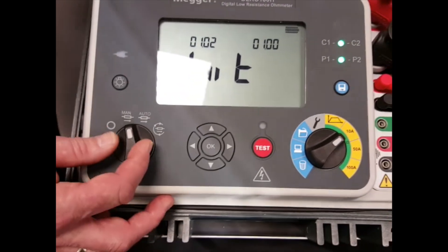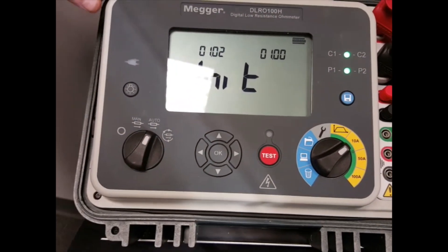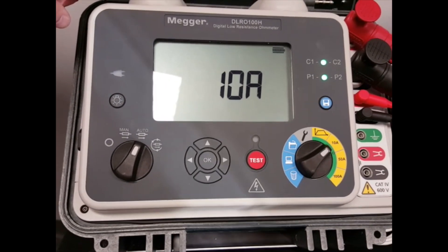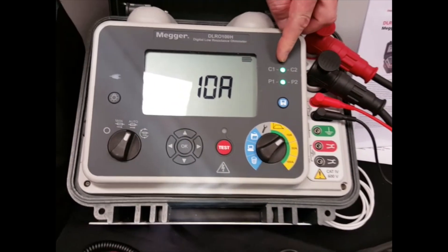In automatic over this side, this test is looking for continuity across the terminals. When you have continuity it will start the test. Here we have some indicators to let you know when you've got continuity. Now here we can see that we have continuity in the current circuit and we have continuity in the potential circuit.